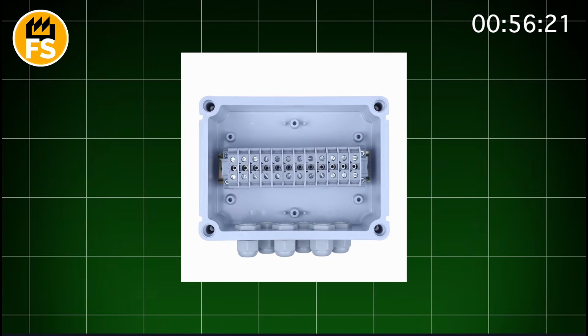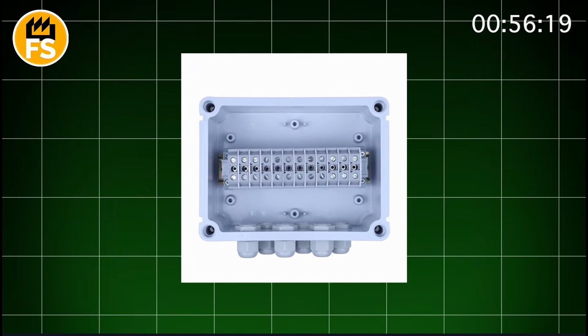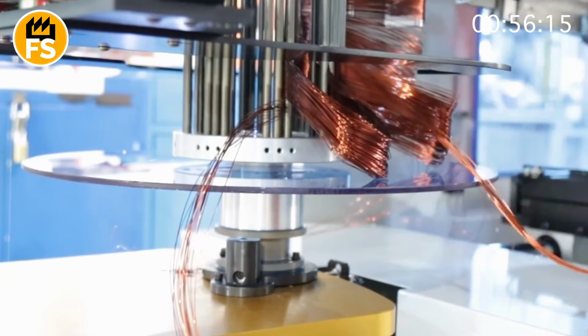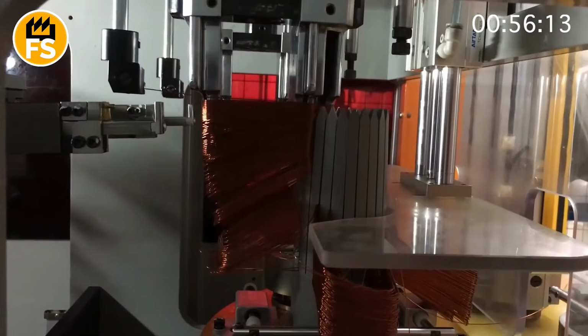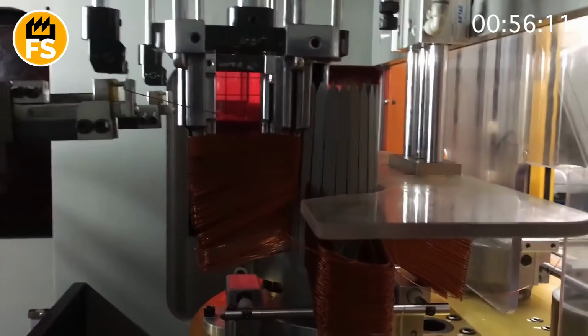The terminal box is on the outside of the housing. This is where the power cables are connected to the stator winding. Inside, contacts, clamping screws, and sometimes temperature sensors.